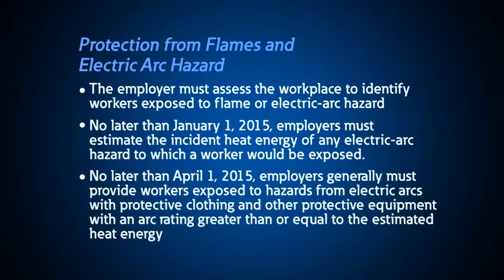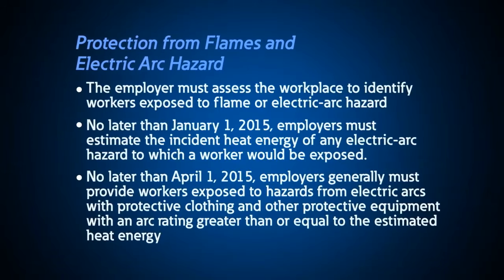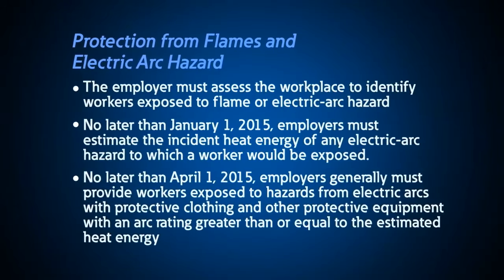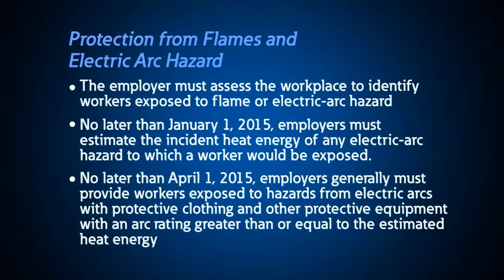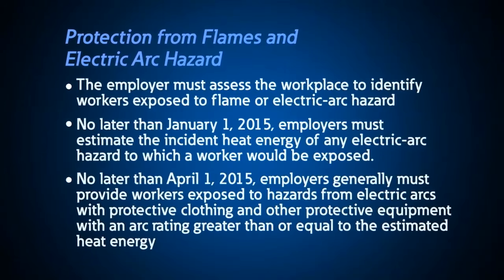OSHA has used the NFPA 70E in the past, following a reported arc flash incident, but more recently has been proactive in their approach to arc flash safety. In 2015, OSHA released a final rule requiring that companies that own and/or operate their own power system equipment perform arc flash calculations and apply labels to their equipment. In addition, it requires that companies provide PPE and training regarding arc flash safety.